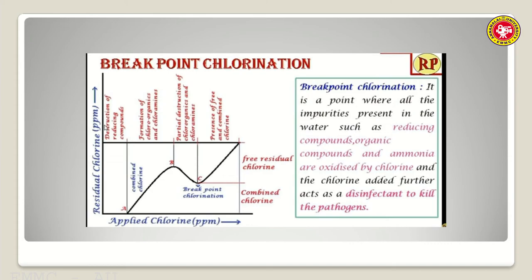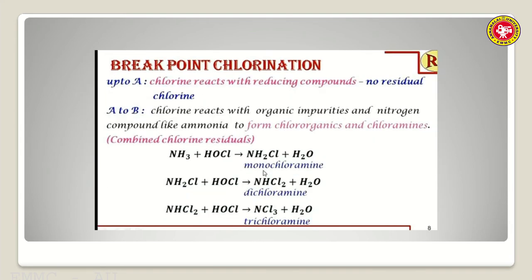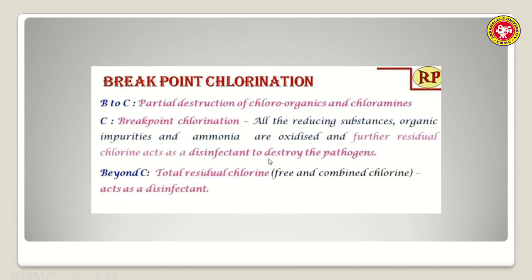The three jobs completed before the breakpoint are: destruction of reducing compounds, formation of chloramines and chloro-organic compounds, and then their destruction. The point at which free chlorine is liberated after all three jobs are done and acts as a disinfectant is called breakpoint chlorination. You must apply chlorine dosage until you reach the breakpoint. Beyond point C, the total residual chlorine acts as disinfectant.